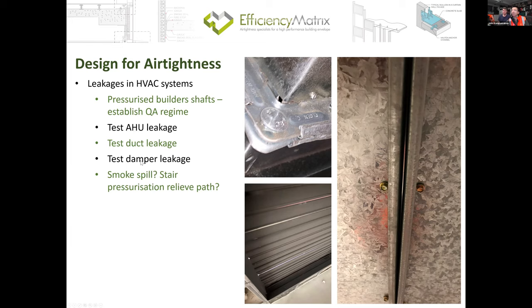The other areas are like AHU, ductwork and dampers. We always see them have a leakage allowance in the specification. But how often do you see a test report on the air handling unit and the dampers? Very, very rare. But because of the requirement on the empirical testing of the building, I think all of you should start asking for the test report on the air handling unit and the dampers. Plus, get the contractor to test a higher percentage of ductwork, not just a 5% test or just two run tests. Try to test as close to 100% of the ductwork as possible.